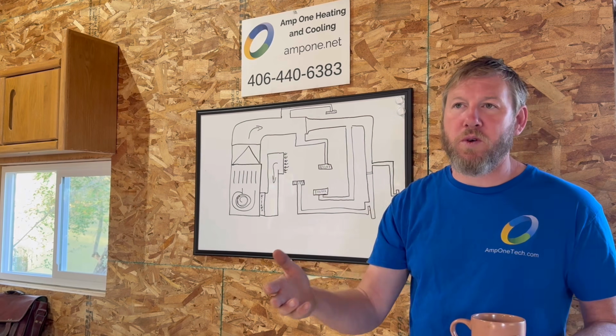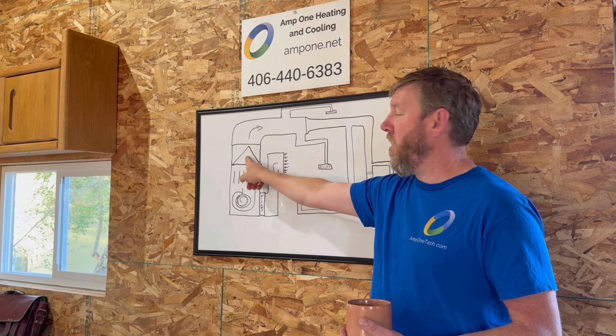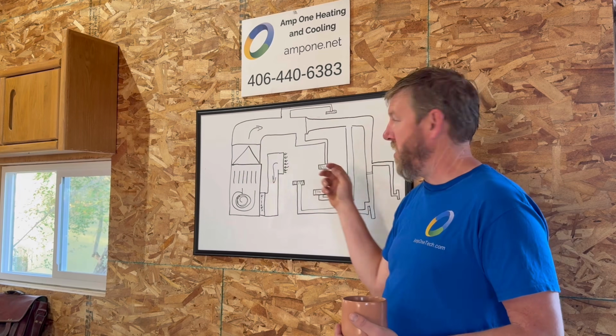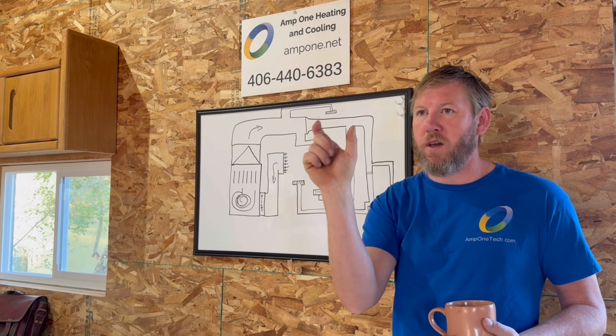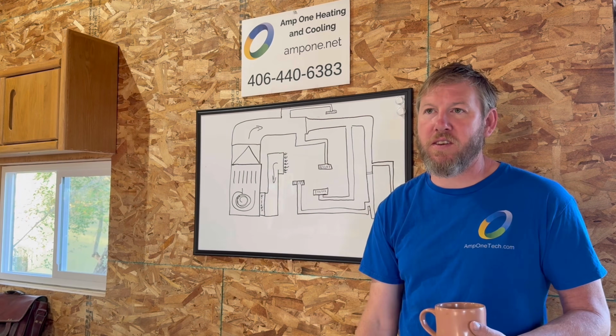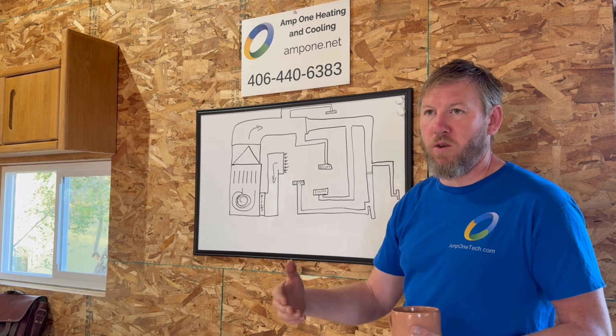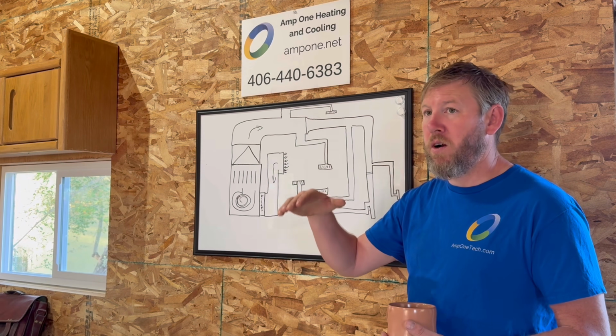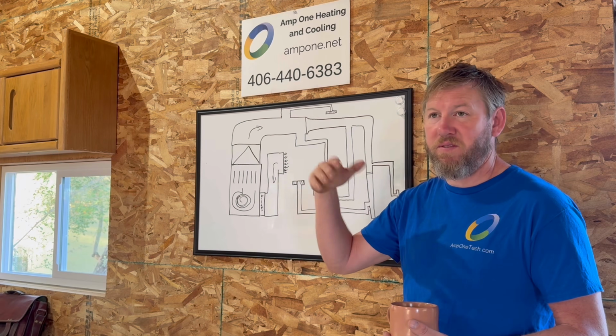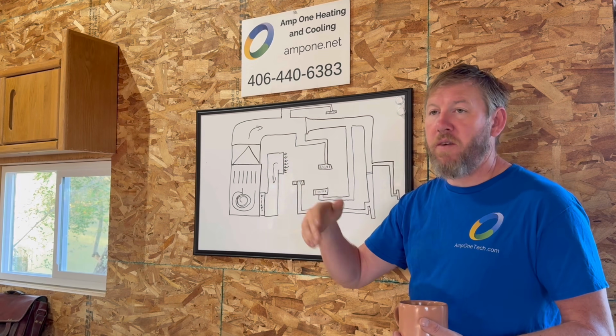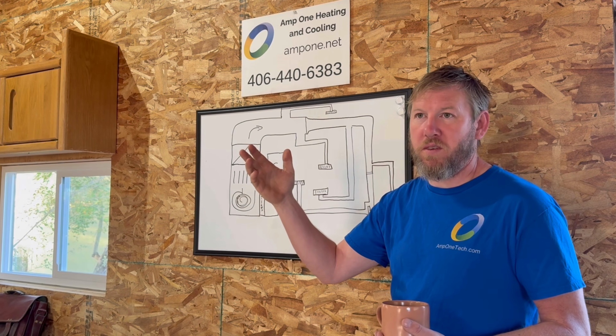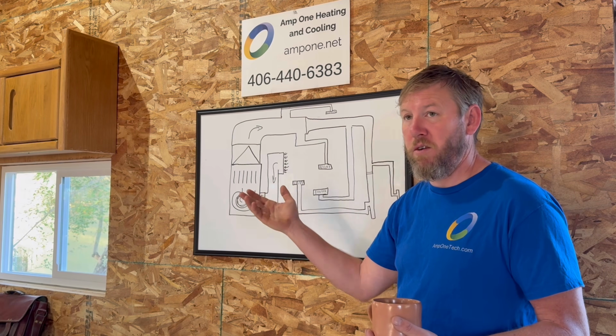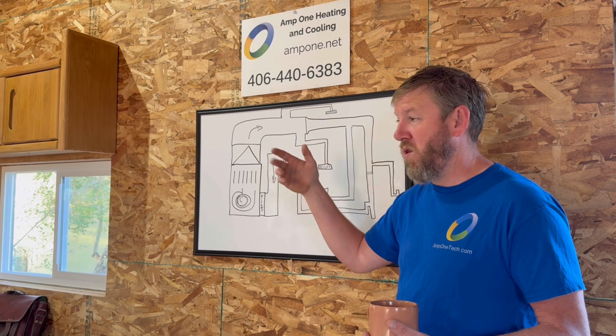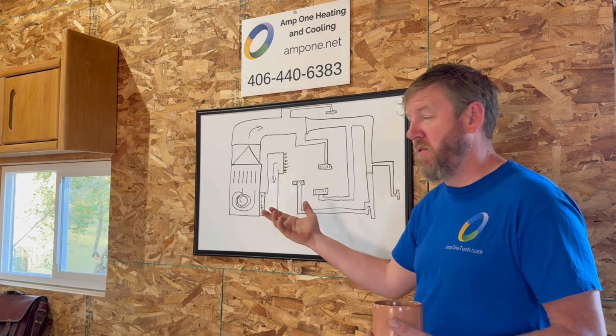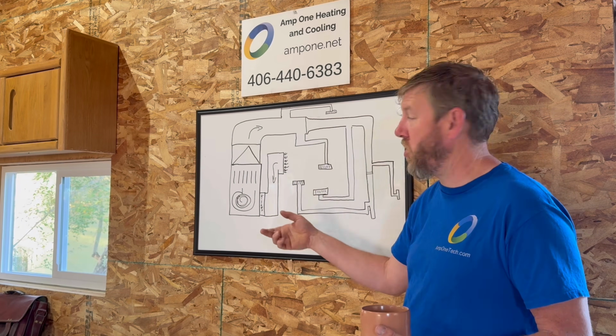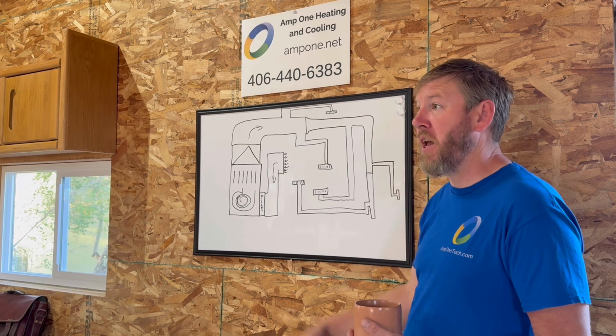So AJ, if you walk up to a system and, where your evaporator coil is, the condensing unit coming in, you'll see a little bulb coming out, then you know there's a TXV on the system. Your superheat is going to be maintained a little better, between 8 and 12, they say. If it's above that, you might have some problems. Either it's a faulty TXV or it's picking up too much heat.